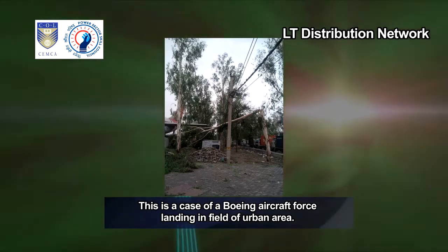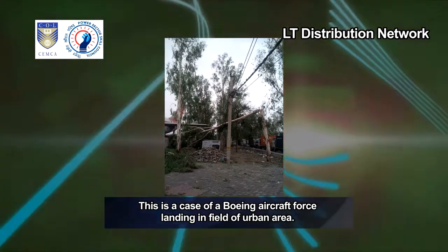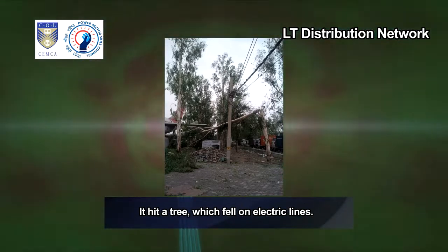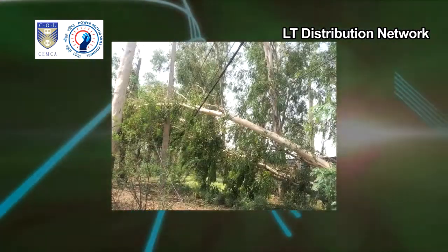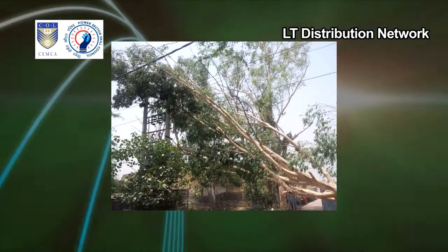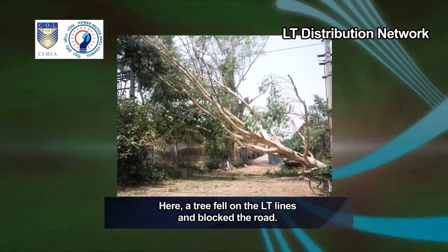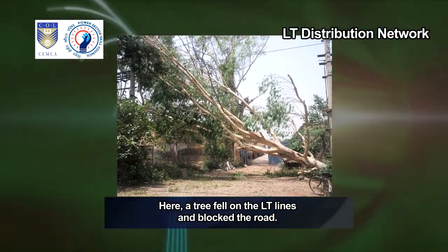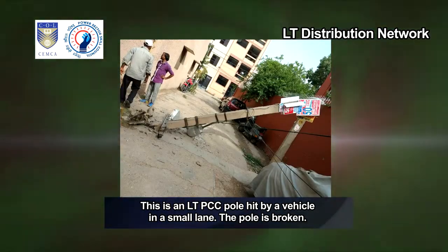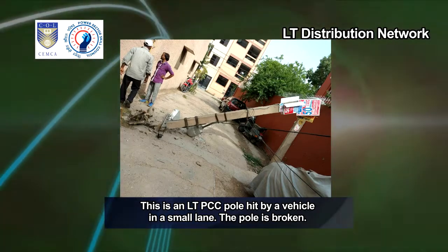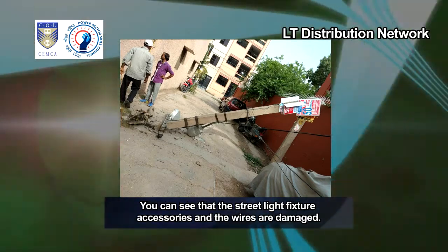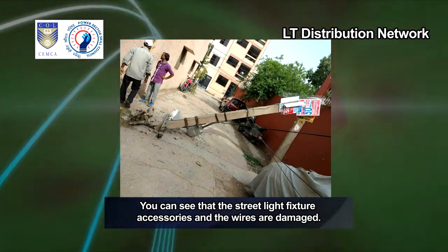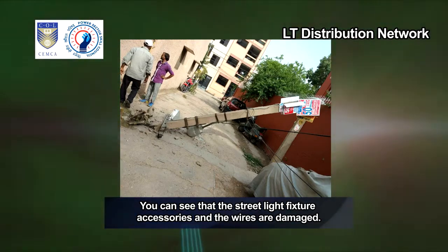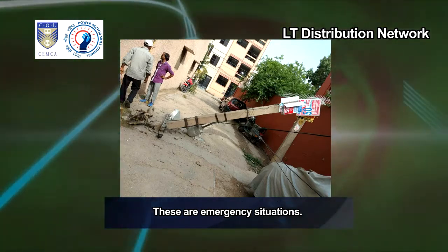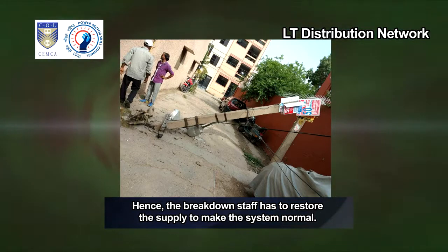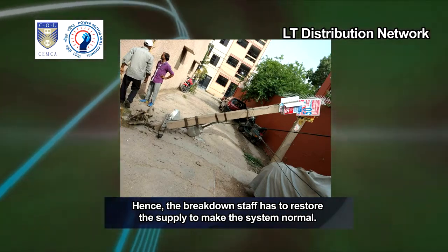This is a case of a Boeing aircraft force landing in a field in an urban area. It hit a tree which fell on electric lines. Here, a tree fell on the LT lines and blocked the road. This is an LT-PCC pole hit by a vehicle in a small lane. The pole is broken. You can see that the street light fixture accessories and the wires are damaged. These are emergency situations. Hence, the breakdown staff has to restore the supply to make the system normal.